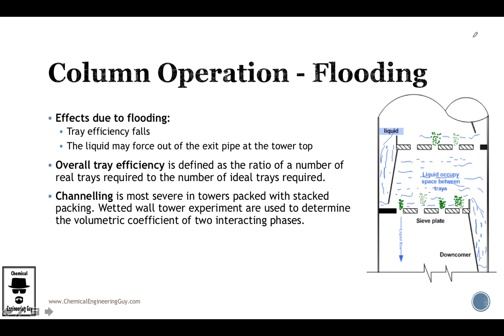Now, what is the main effect besides you are actually not having the correct mass transfer operation between liquid and gas? Well, you will have a drop in tray efficiency. So remember that typical tray efficiency is 50%. Maybe you will drop it up to 5%, 10% and so on.